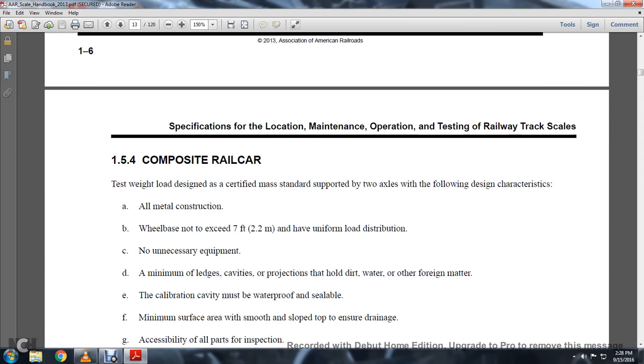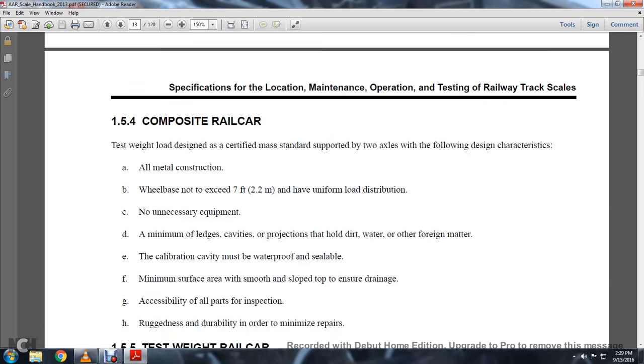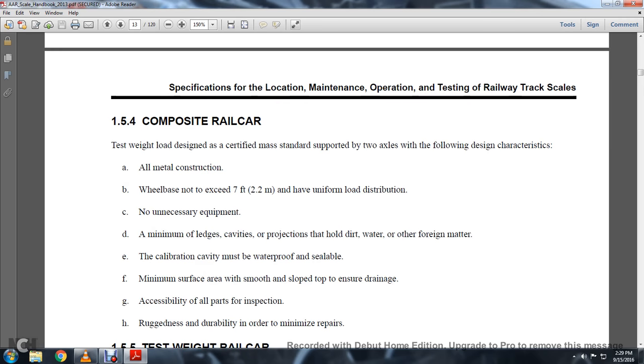1-5-4: Composite Car. The test weight load design and Certified Mass Standard is supported by two axles with the following design characteristics: all metal construction with wheelbase not exceeding 7 feet, having a uniform load distribution, no unnecessary equipment, minimum ledges, cavities, projections, and holes that hold dirt, water, and other foreign matter. The calibration cavity must be waterproof and sealable. Minimum surface area with smooth slope top for drainage, accessibility of all parts for inspection, and ruggedness and durability to minimize repairs.